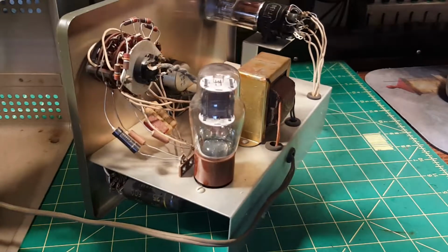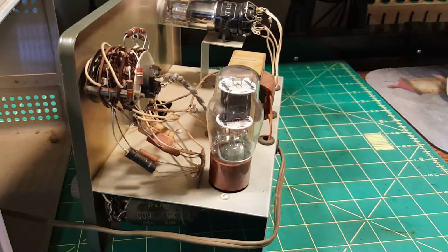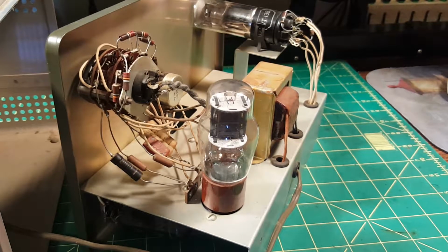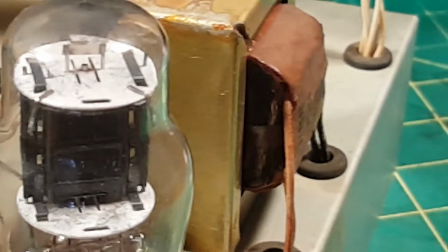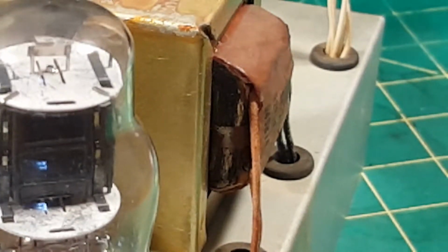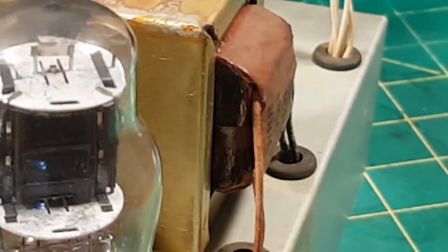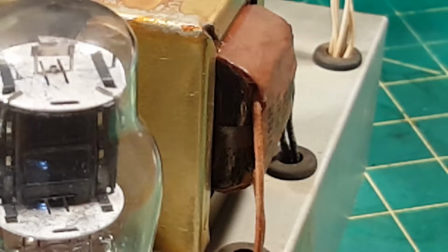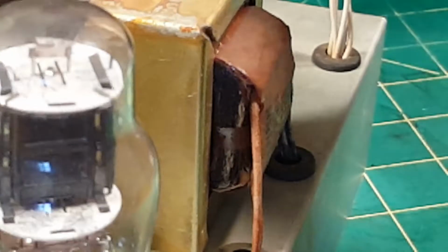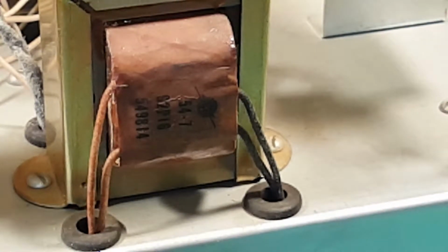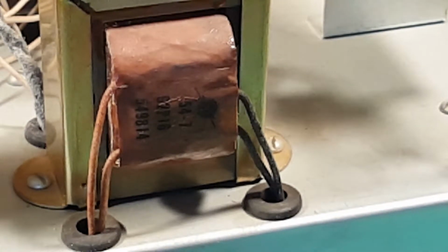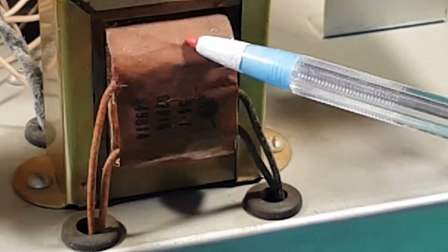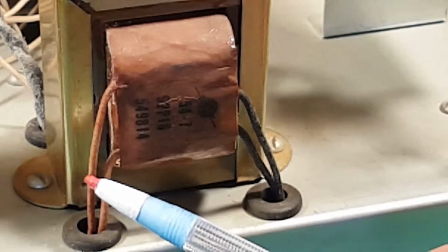I'll look in the end of the transformer core - yeah, you can't quite see, the lighting isn't adequate - but I'll check the condition to see if it looks overheated. I'll also look at the color of the protective tape over the paper on the core, check if it's brittle or cracking apart. This one is not, and I check how flexible the wires are.